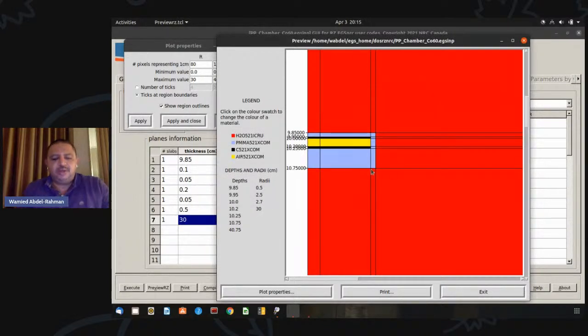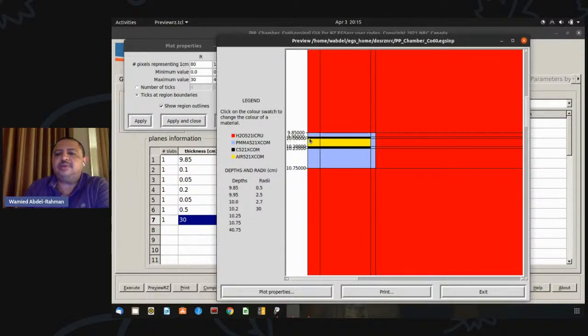Okay. So now this is how it looks. We have air in the middle, and you see below the electrode, it's going to start at 10 centimeters. So this will give me the dose at 10 centimeters, or that's the effective point of measurement. So the dose in Monte Carlo is actually going to be reported at 10.1, because this thickness is 2. But that point, that dose in phantom, represents the dose at 10 centimeters, because the effective point of measurement is below this window.